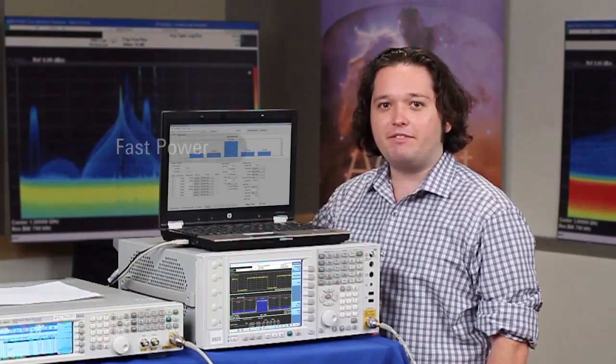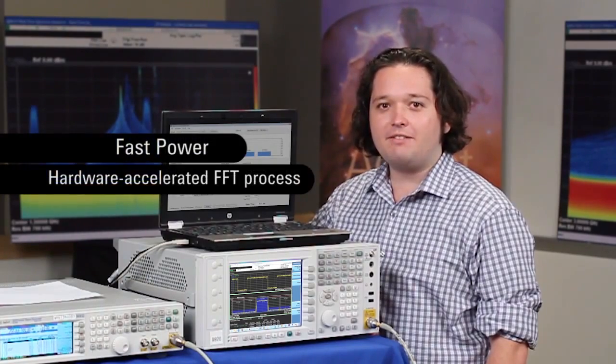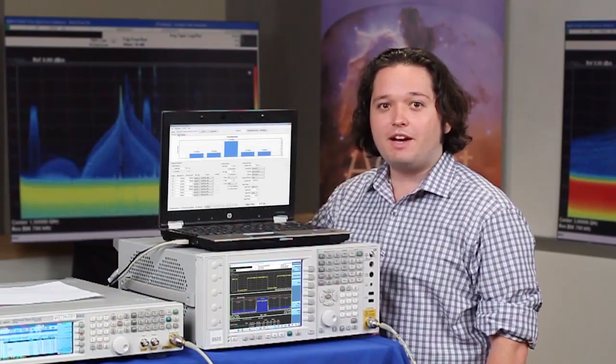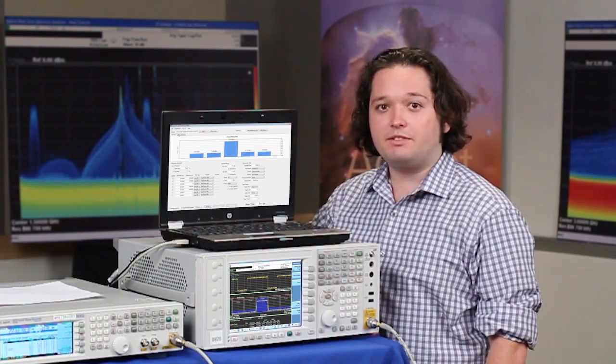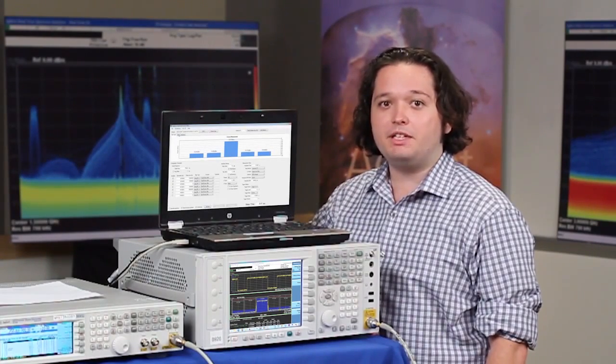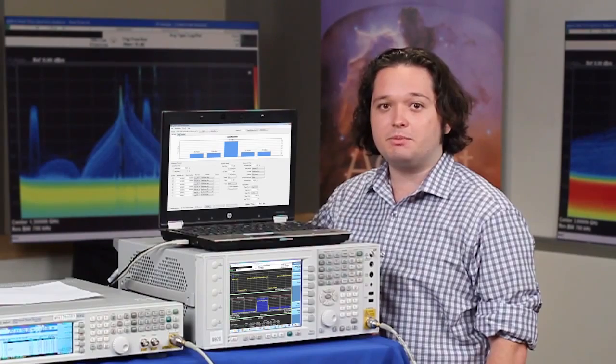Today I will show you how to implement FastPower, a hardware accelerated FFT process to perform a standard ACP measurement. Using the FastPower trigger delay feature, time gating can be implemented for various LTE TDD measurements.